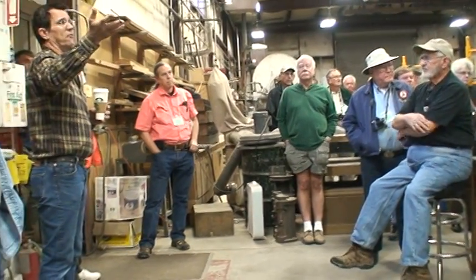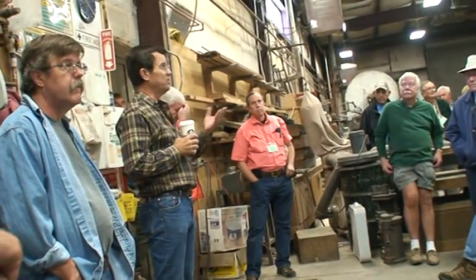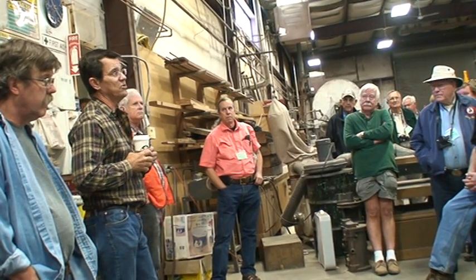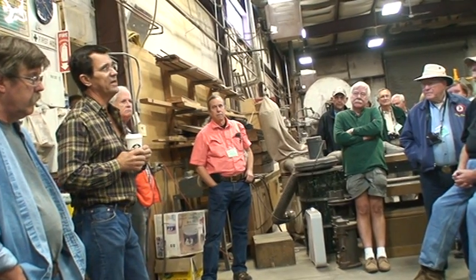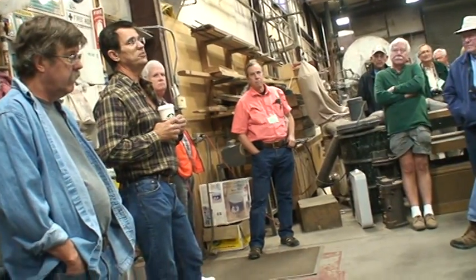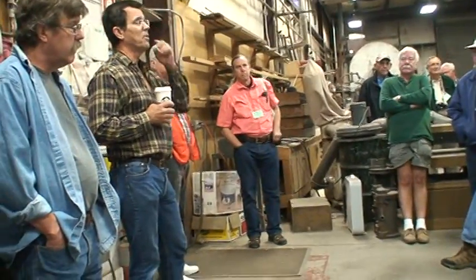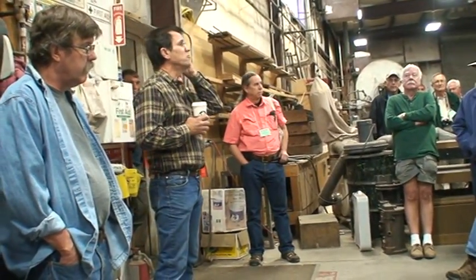We reused, for instance, this is the extent we've gone to. So we took out the front tube sheet and we looked at it. Visually, it looked pretty good. So we sandblasted it and we dye penetrated all of the ligaments between the tube holes inside out looking for cracks, and that was good. So then we polished the edge of the sheets and we dye penetrated, inspected the edge of the sheets looking for delaminations, and put new studs in it, reamed the holes to uniform size all the way around, put it back in. So the tube sheet was iron, this is steel. There were iron parts on this. Well, actually, let me think. No, this whole thing is steel, but there were iron rivets.